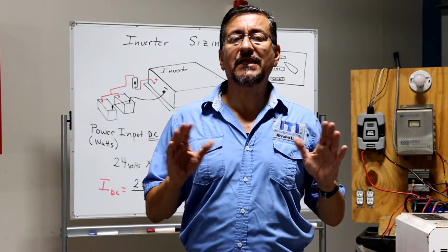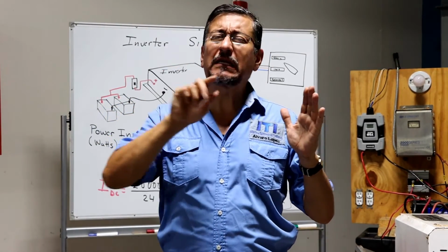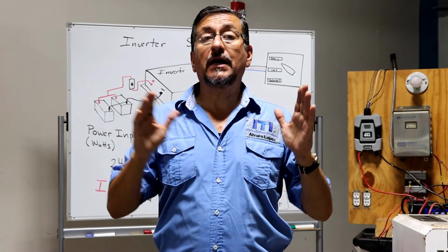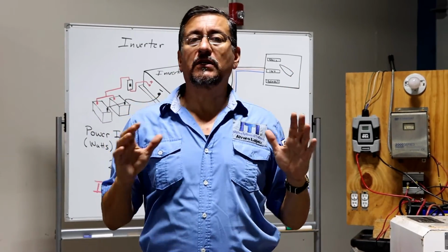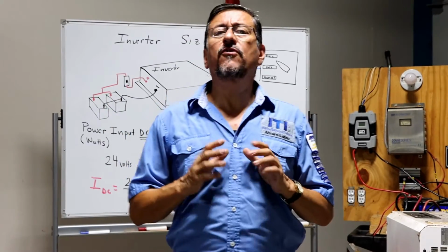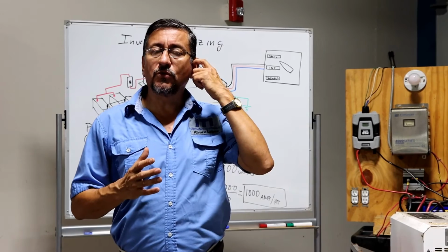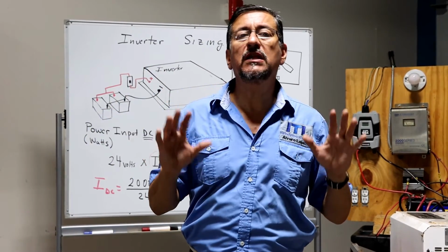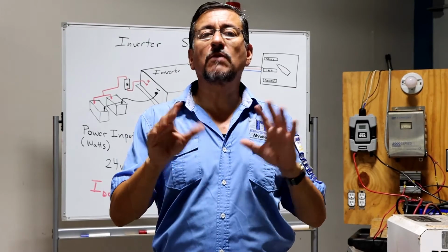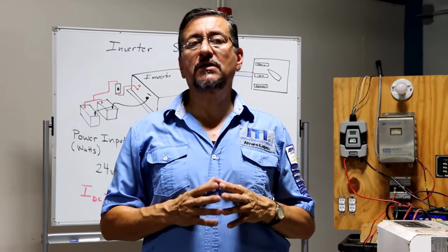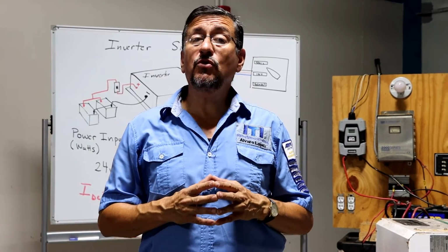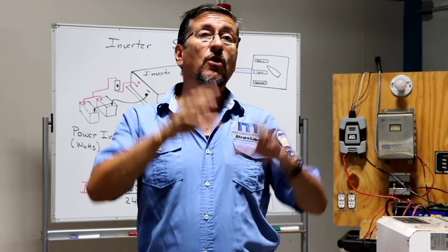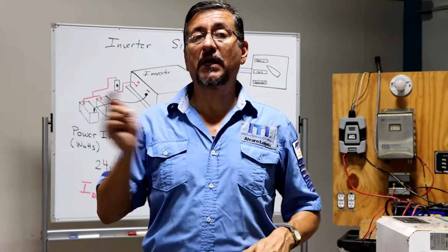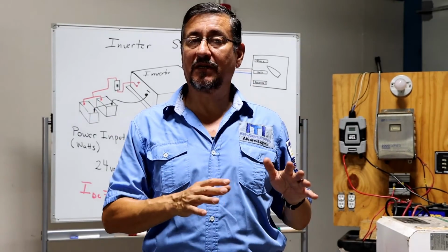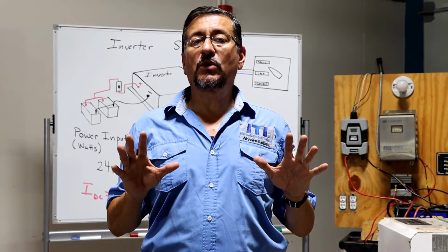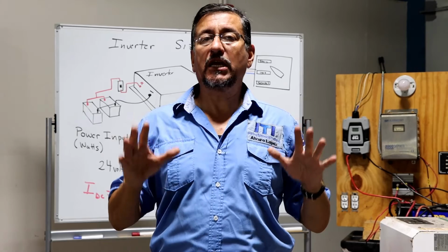The inverter has a couple of inconveniences. One inconvenience is that the output signal is not a perfect sinus signal, it's like a little square, and additionally, the output signal from the inverter doesn't have frequency. For that reason, the power produced by the inverter is used only in emergency, and for some equipment, not for all the breakers in the AC panel. Why? Because if you use the power produced from the inverter for all the breakers, you need a lot of batteries to supply power for those equipments. I am going to explain right now the procedure to calculate the capacity of the inverters in kilowatts.